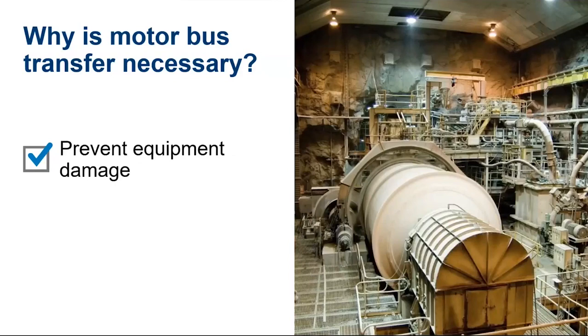One of the main causes of equipment damage from a power outage is electrical surges when the power is restored. For example, if you have a lumber mill operation where logs are cut and you have a power outage while a log is in the machine, you run the risk of jamming the machine. This condition, combined with the surge in power when the power is back, can result in severe equipment damage due to thermal overload. The same thing can happen for any motor under heavy loads. If a successful transfer is achieved, the motor would never stop. Your process will never stop. Therefore, you're mitigating the risk of damaging the equipment.